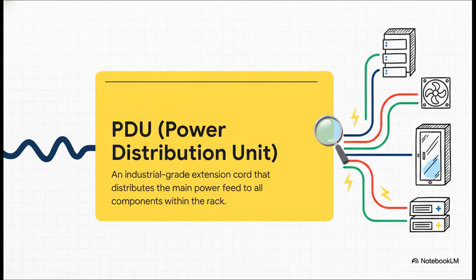All right, next we have the PDU, or Power Distribution Unit. The easiest way to picture this thing is as a giant, incredibly smart, industrial-strength power strip for the whole rack. It takes that main power feed and makes sure it gets safely distributed to every single component, from the power shelves all the way down to the cooling fans.